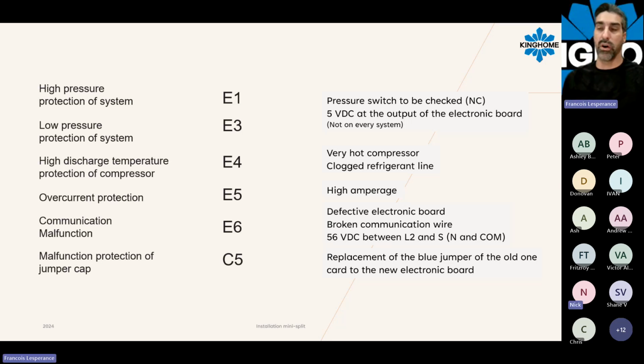E5 is related to overcurrent protection. So whenever the amperage is really, really high on the system, for example, because you have a stuck compressor, or you have some problems with the drive board, well, the E5 will tell you that you have a high amperage problem.